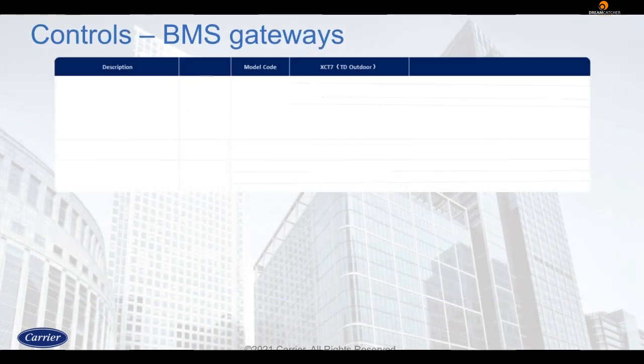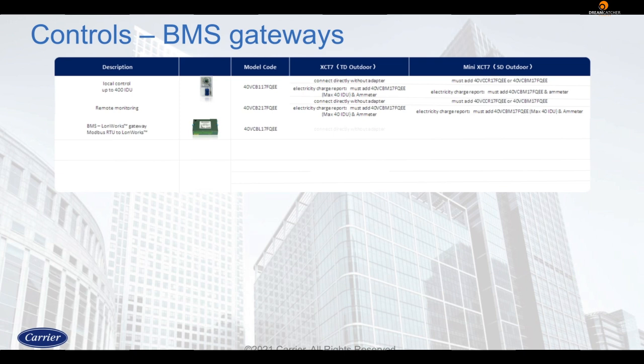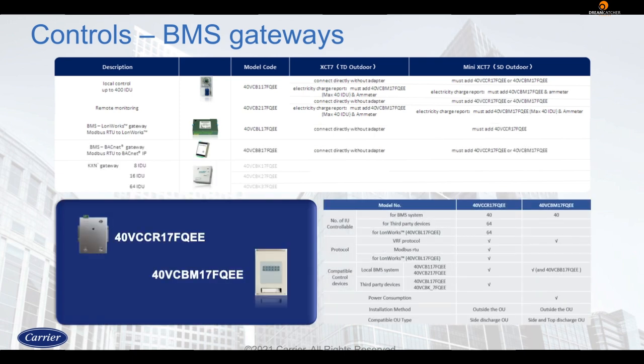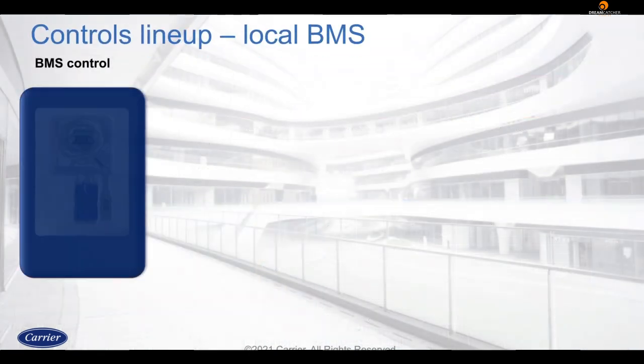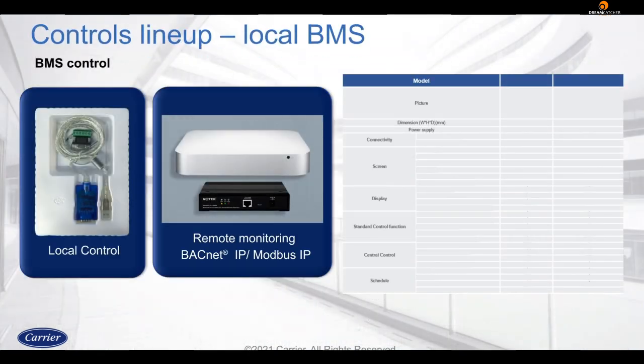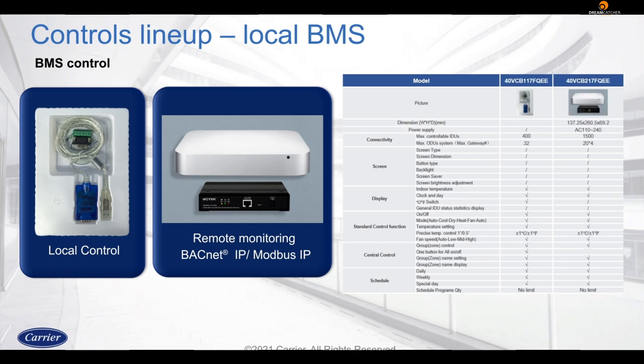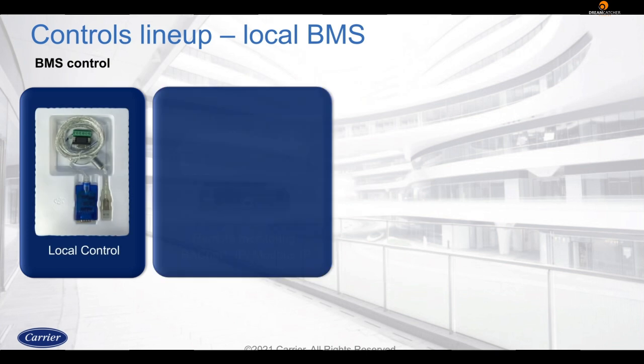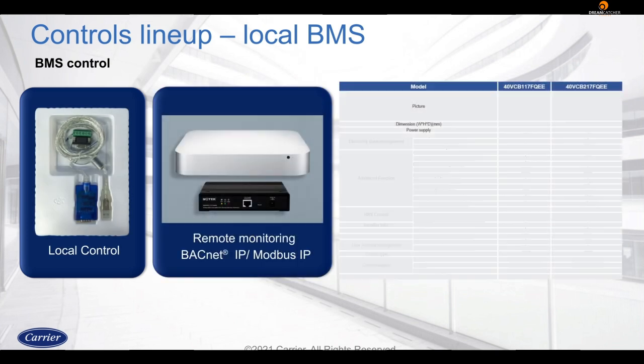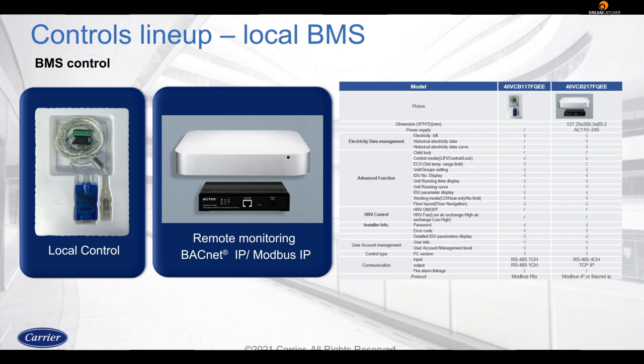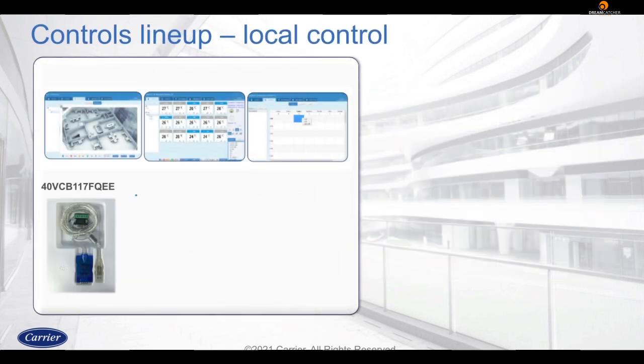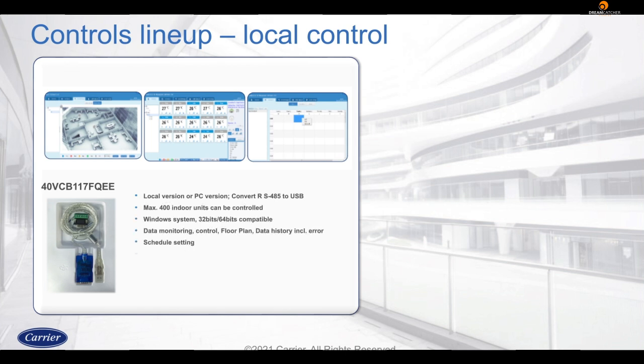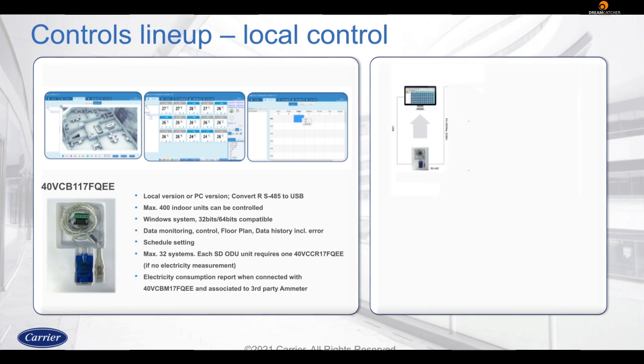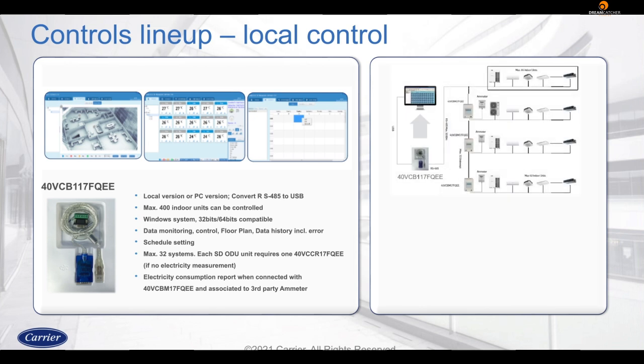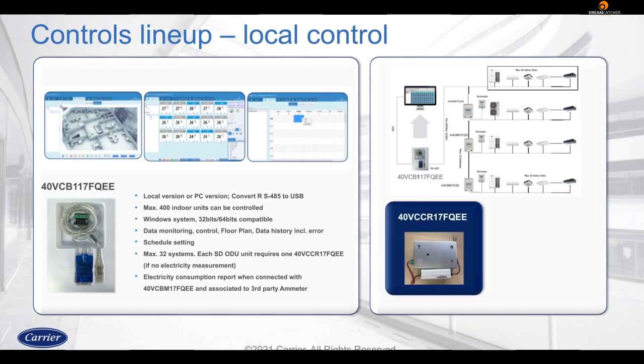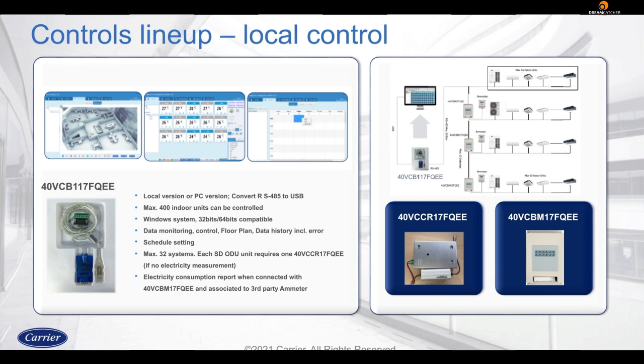The BMS gateways offer connectivity to various BMS modules as per the requirement of the system. The XCT7 comes with local BMS control, which also gives a feature for remote monitoring via BACnet Modbus IP. The local control option for the XCT7 runs on Windows systems and can control up to 400 units. It offers options for data monitoring, control, floor plan, data history, and schedule setting as well. It can even generate reports of electricity consumption when associated with a third-party ammeter.